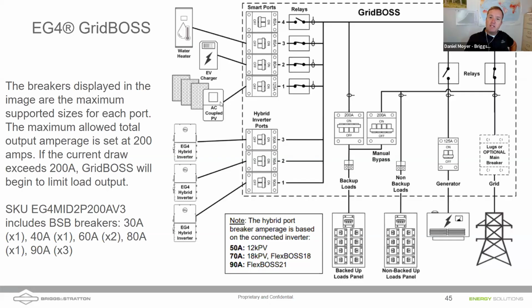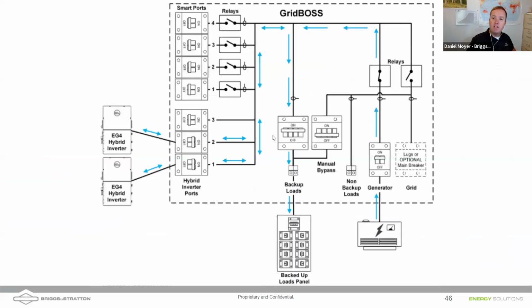AC coupled solar makes it really easy. We bring that into a smart port on the grid boss. We can additionally bring in smart loads, which will open up based on the state of charge of the battery. One value add is that if I had multiple inverters, I would need load centers to combine their AC output and input, but that's all done internally now in the grid boss.